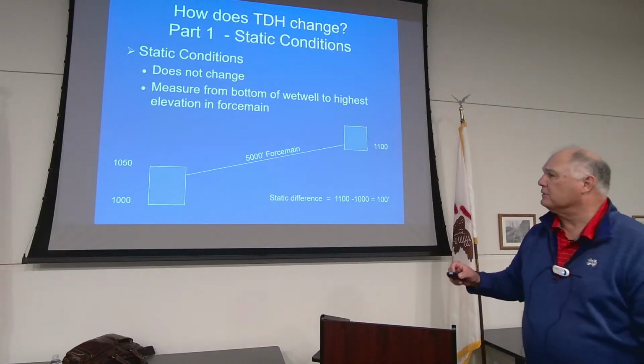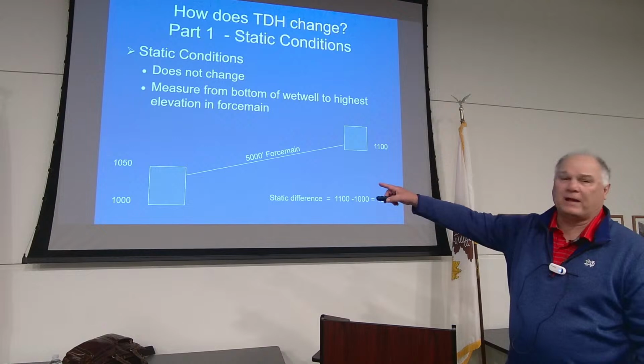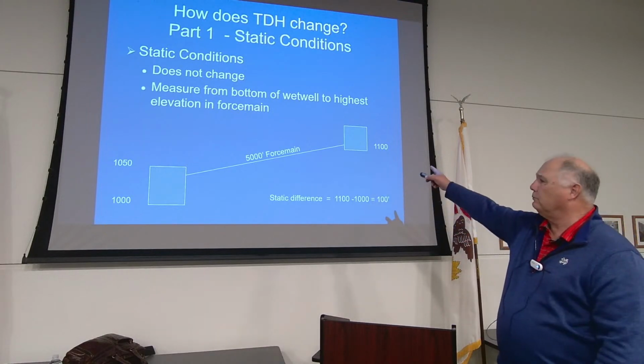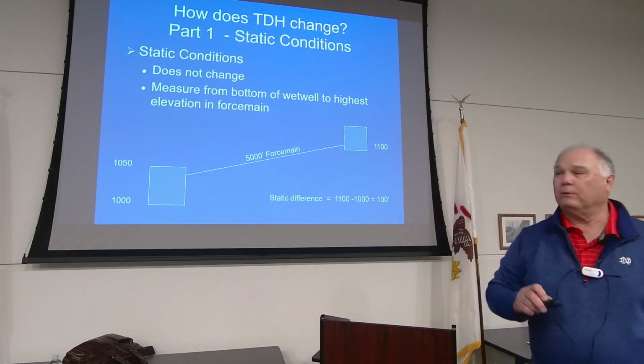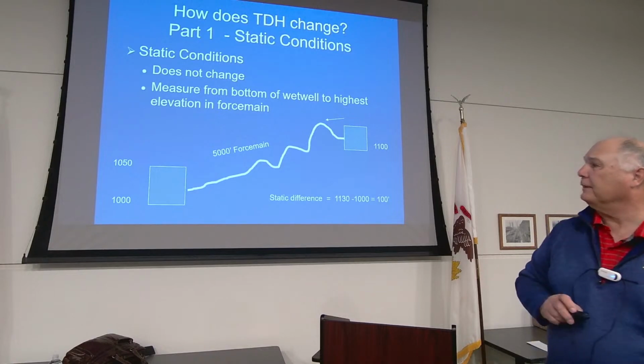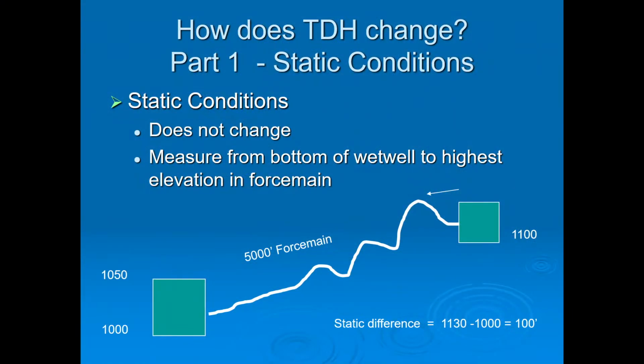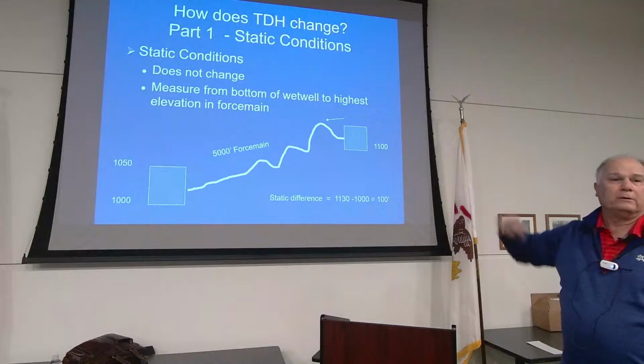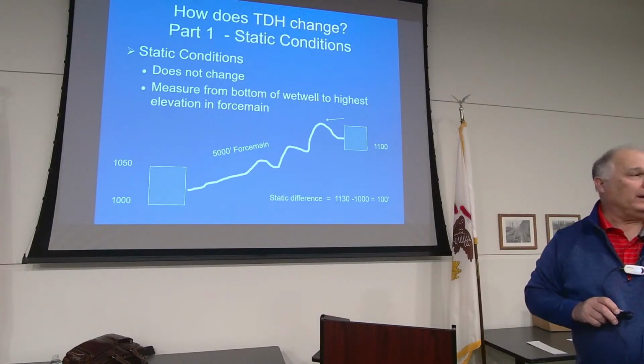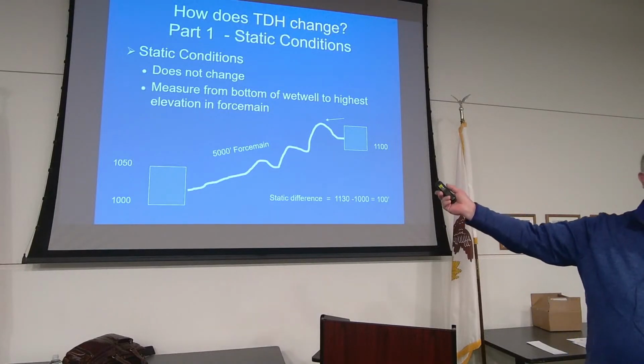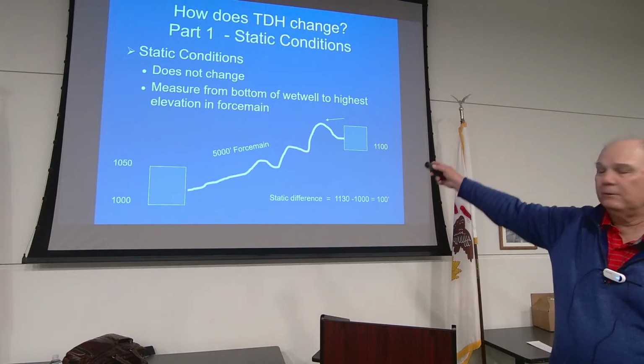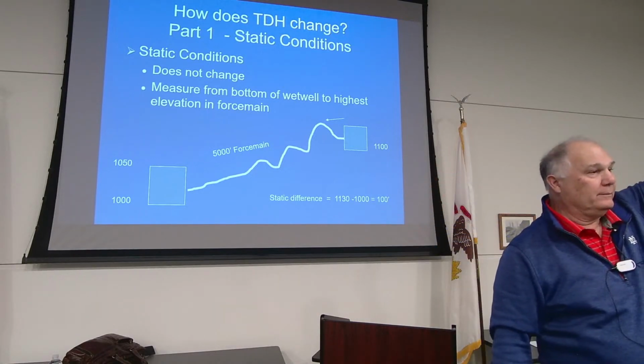In this condition, I've had some engineers tell me it's got to be from the top of the wet well to the highest point. They would not be right. If we look at this condition, we could say, okay, we've got a force main going up like this, then our highest point is above our 1100. So we've got to be careful of all that. What do we put at each top of these little rise points? We put an air relief valve.